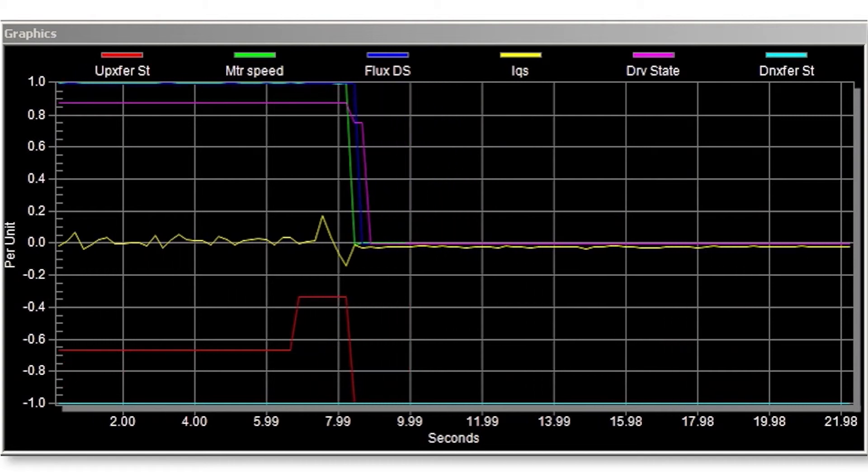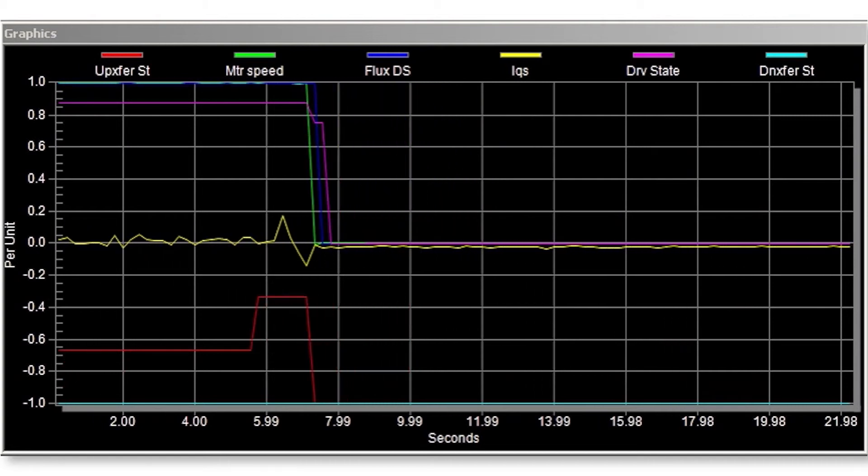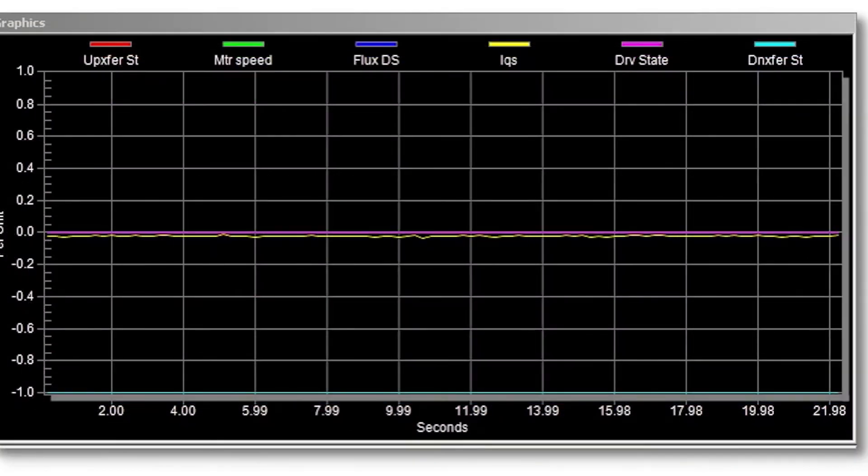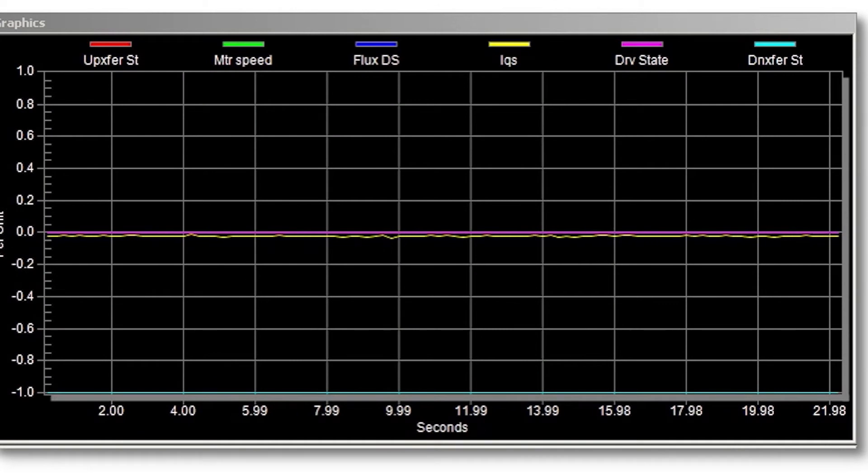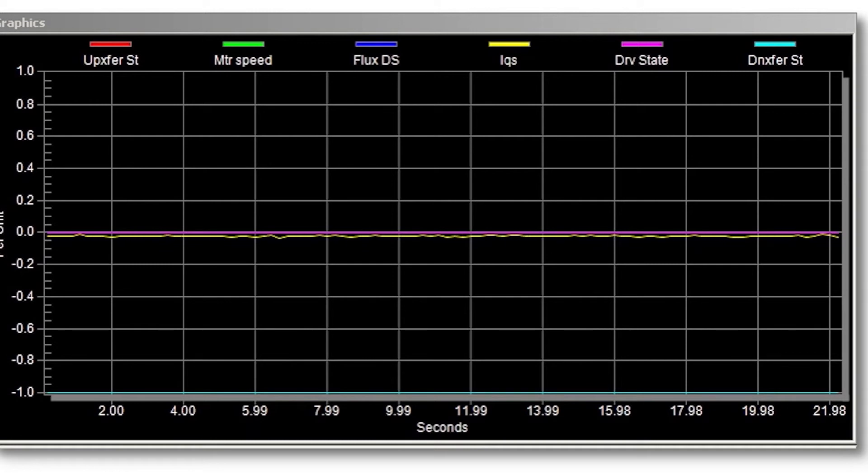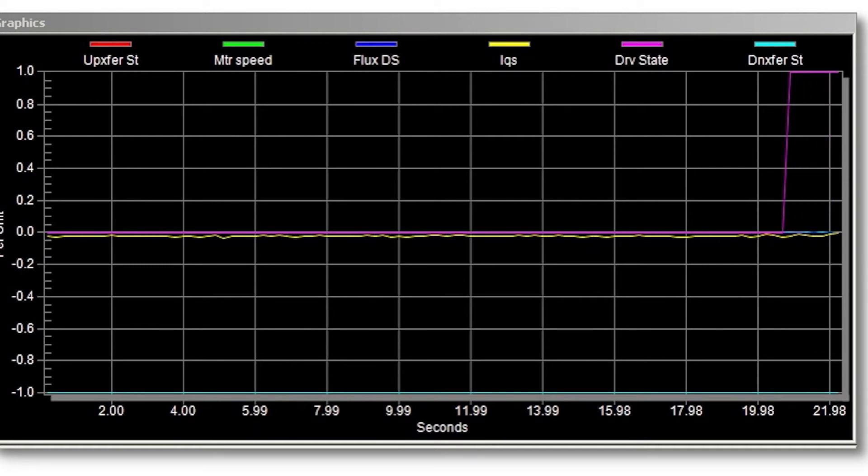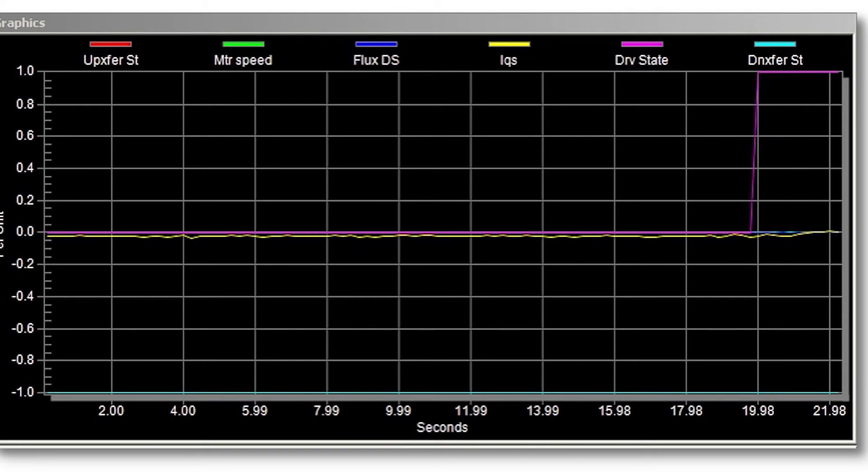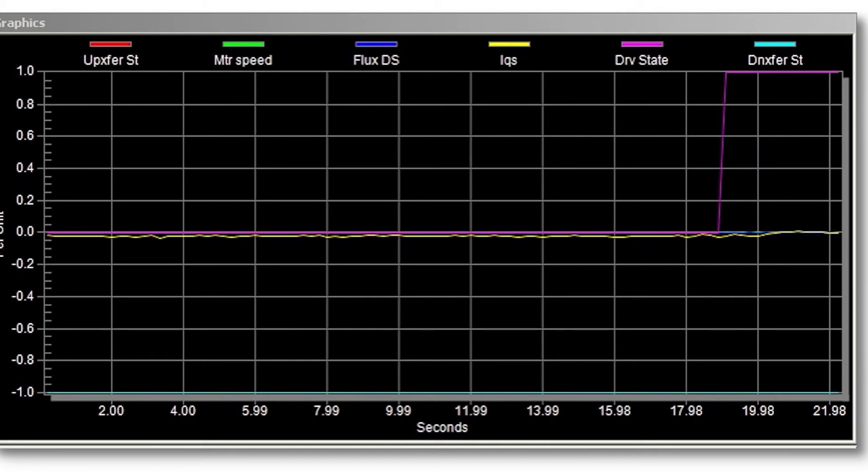The down transfer sequence is almost identical to an up transfer. The motor will be taken off the line and connected to the VFD for variable speed operation. The drive is turned on and as shown in the trace is ramping up to 60 Hz. No torque is appearing yet because the current is being provided from the line.